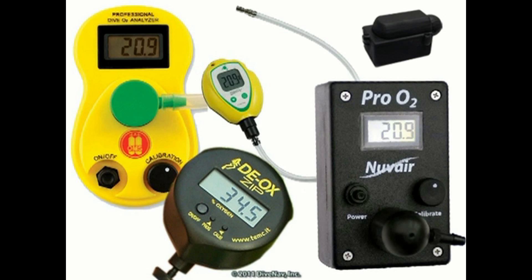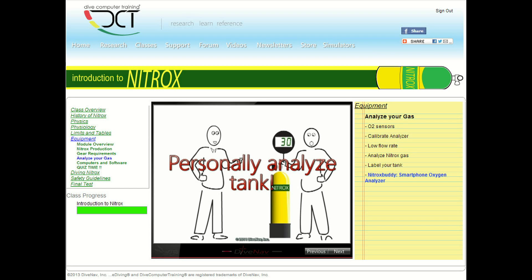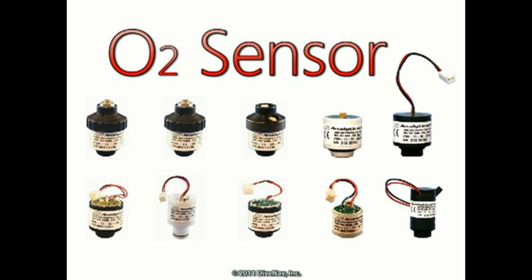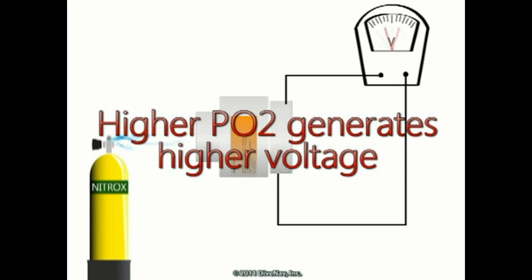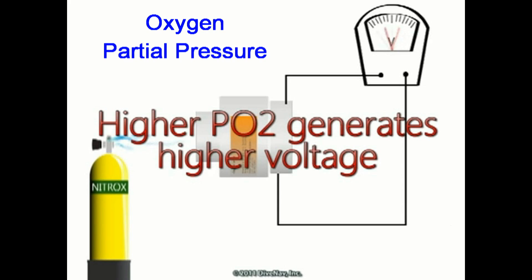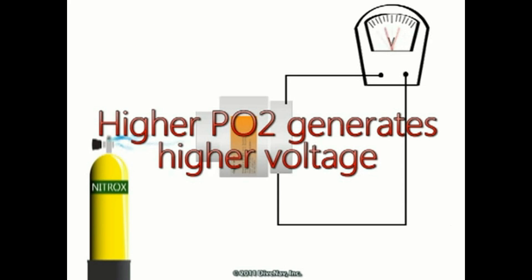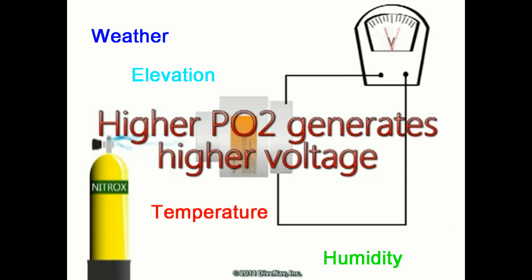On the other hand, an oxygen analyzer is affected by several environmental variables. At the heart of every oxygen analyzer there is an oxygen sensor. The oxygen sensor is a chemical device that measures the partial pressure of oxygen, and as such it is affected by changes in atmospheric pressure, temperature, and humidity.